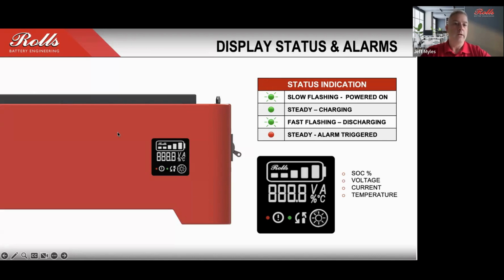If it's a condition where the battery is attempting to operate in temperatures which exceed the constraints that have been preset by the BMS, then that's going to be recorded, and it's going to be noted that there was an attempt to make a charge on the battery and it was below the temperature constraints. So in those conditions, that will be logged. The batteries do not log all conditions all the time. So under normal operation, it's not going to be recording information in a log. It's only going to be in the state of an alarm condition.